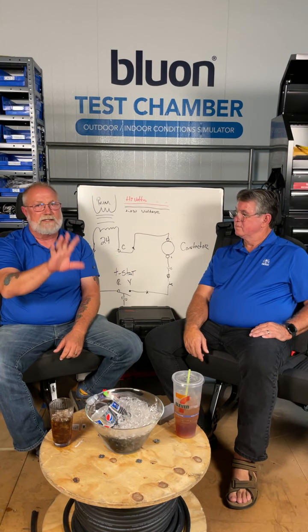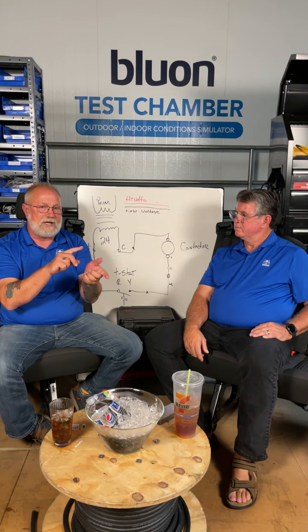So to answer that gentleman's question a little bit more specifically, once I saw that everything was working at the air handler, knowing that I turned the thermostat down, now I can check my voltages going to the thermostat. I can check my voltages coming back from the thermostat. I can jumper and see if the condensing unit will run. You can do a lot of troubleshooting right there at the furnace or air handler. Pretty much you divided and conquered.